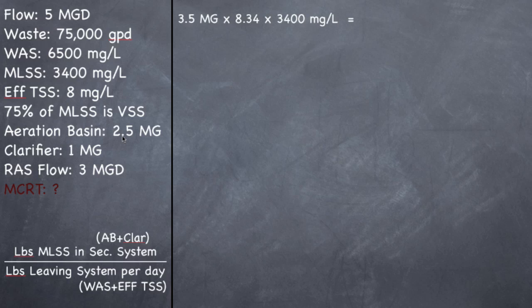So 2.5 million gallons plus 1 million gallons equals 3.5 million gallons times 8.34 pounds per gallon times 3,400 mixed liquor suspended solids milligrams per liter. And when you multiply all that out, you should get 99,246 pounds of mixed liquor suspended solids in the secondary system. That's the top part of the formula.